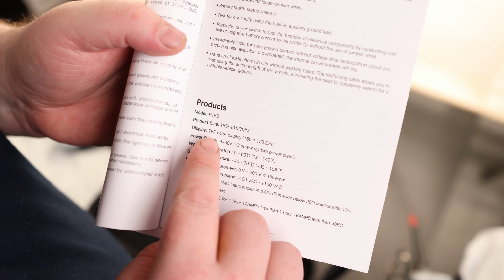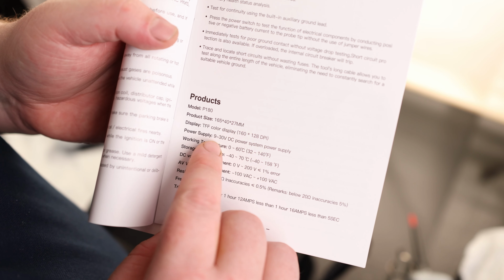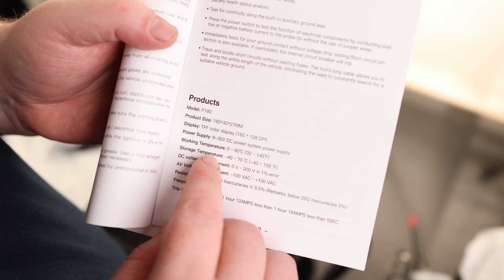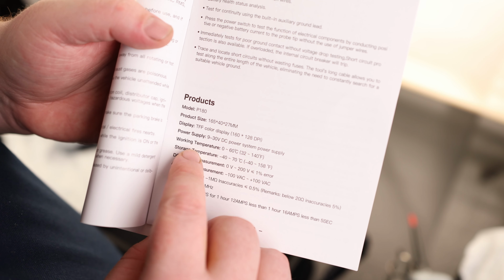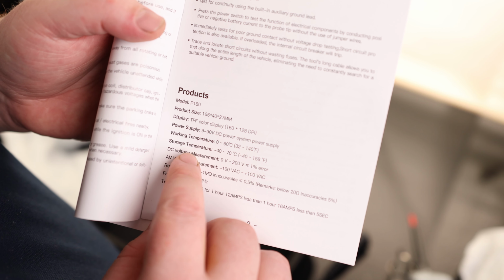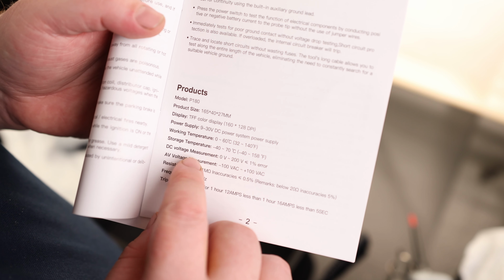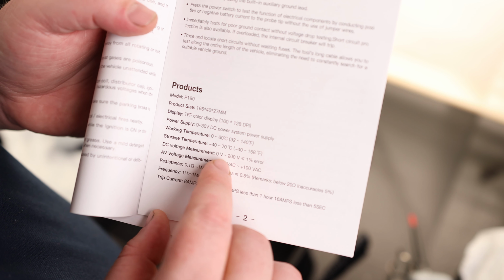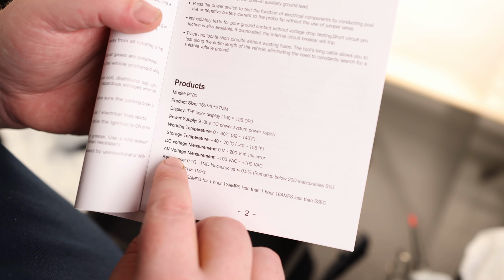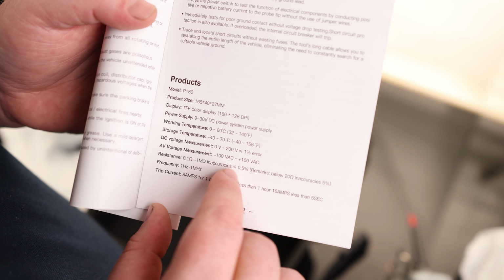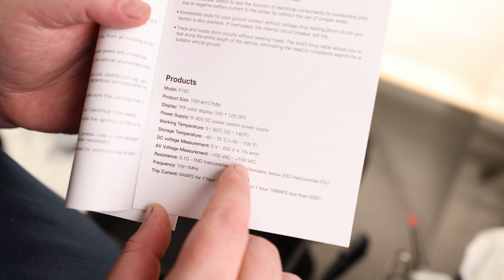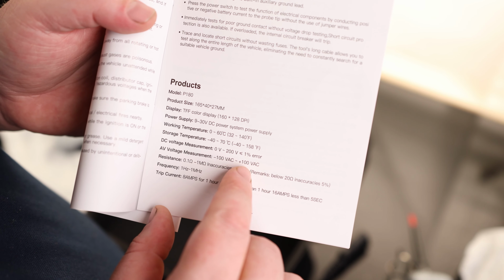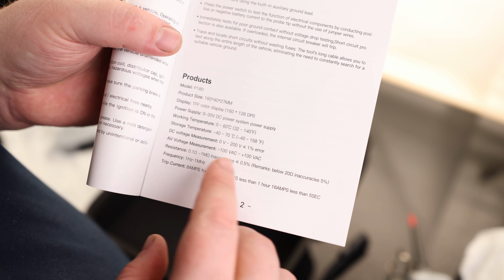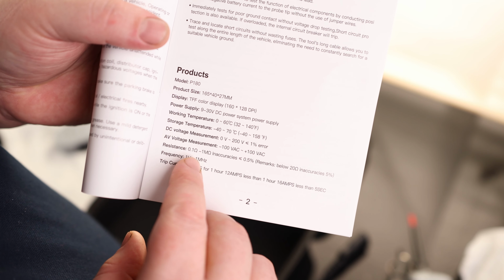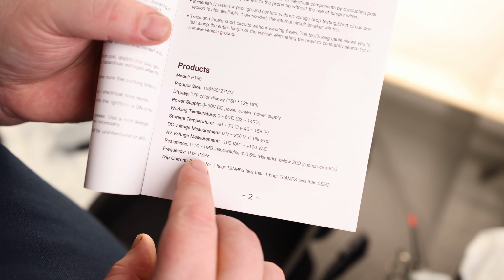It uses a TFT color display that can be powered from anywhere between 9 and 30 volts, so if you're using a 24-volt battery that'll still work. Working temperature is 0 to 60 degrees Celsius, storage is negative 40 to 70 degrees Celsius. DC voltage can check from 0 to 200 volts, and AC voltage from negative 100 to positive 100 volts AC. That's not 120, so you won't really use this for household current, but it's nice to know you can check full wave AC. Resistance is 0.1 ohms to 1 mega ohm, frequency is 1 hertz to 1 megahertz.